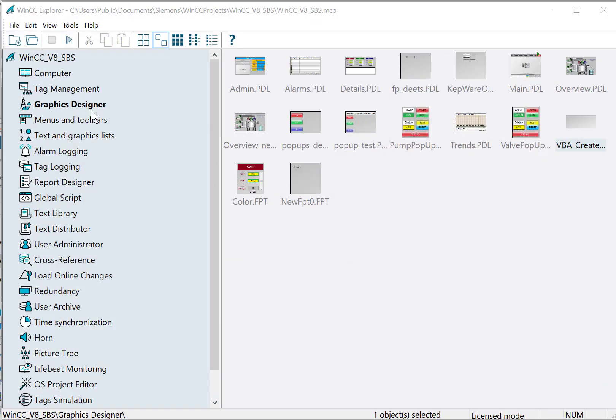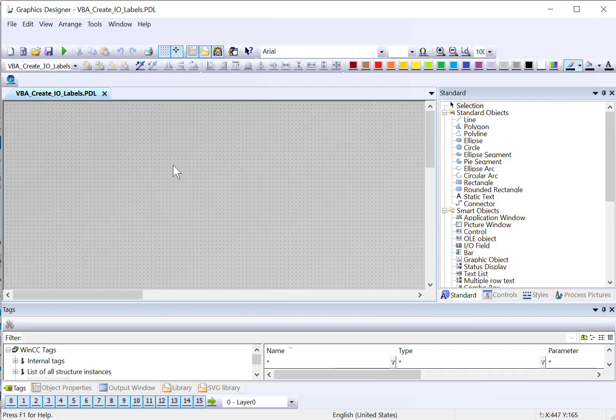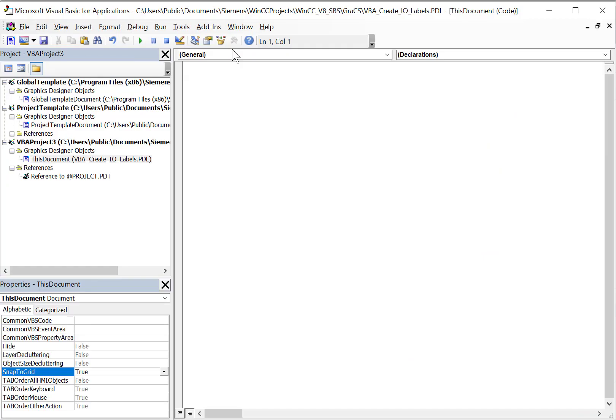We're going to start in Graphics Designer. I've just created a blank page to add this VBA script. The first thing we're going to do is open the Visual Basic for Applications editor. As it turns out, the PDLs — which are your graphic screens in WinCC — are VBA forms, so we have a lot of benefits that come with that. We can know when HMI objects are added to the screen, when they're moved, when they're removed, and we can write VBA code to react to those events.